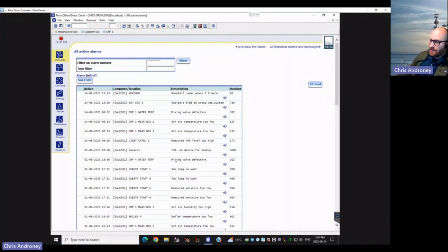It's not an actually working system, but for everybody, I recommend, we want to see a green alarm button here, meaning no alarms, because no alarms means that all of the alarms that come in after are important. They're dealt with immediately, and you don't get that alarm fatigue sort of thing where you just have a bunch of alarms here and you tend to ignore them, because when you do get alarms that matter, you want to be able to deal with them and notice them right away.